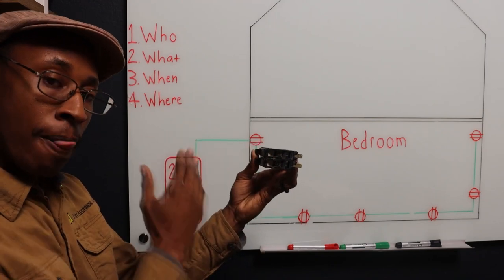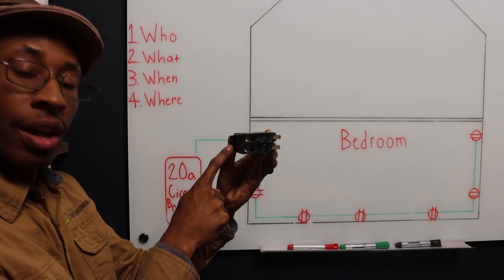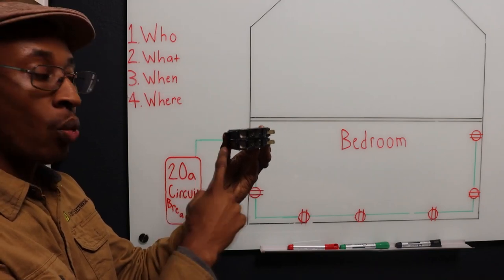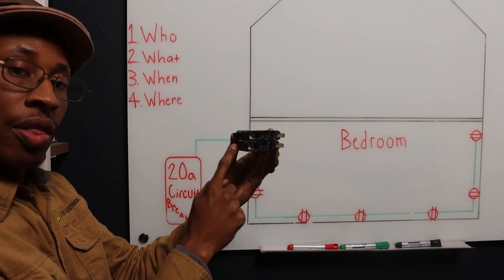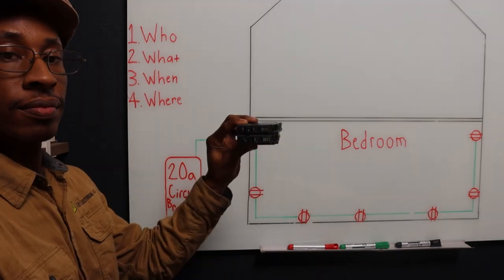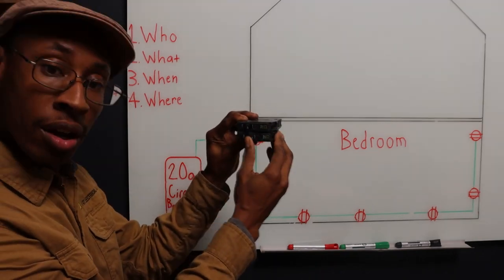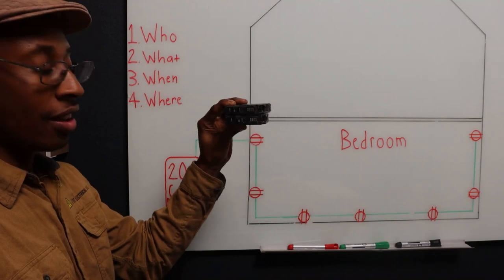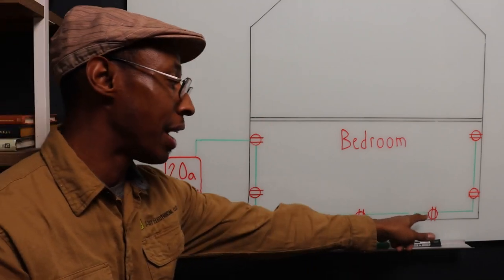Turn that breaker on. If that breaker stays on with the wire you took out of here and it's currently on here, if it stays on, that means you have a bad breaker. If that breaker trips now, that confirms to me that I have an issue down the line in the house somewhere.